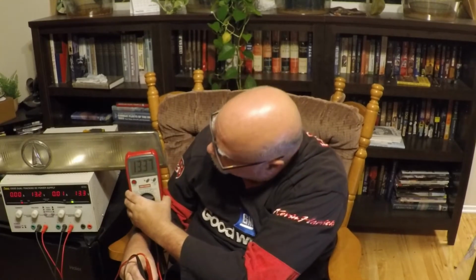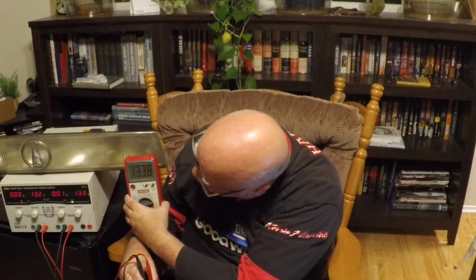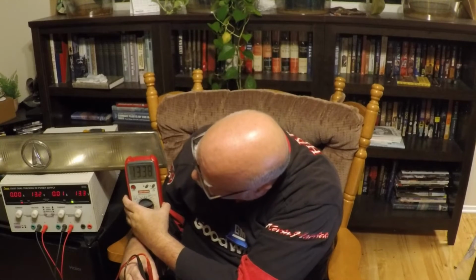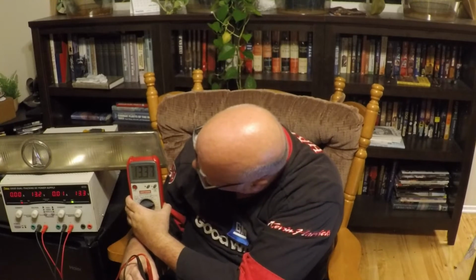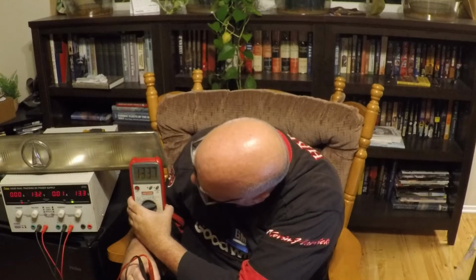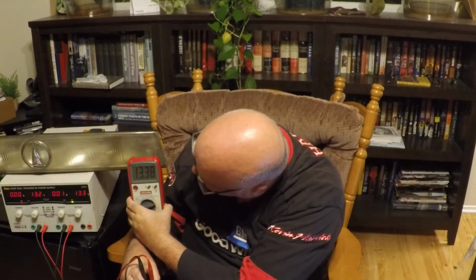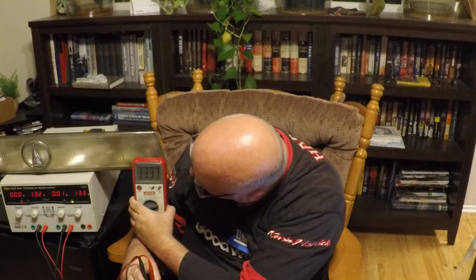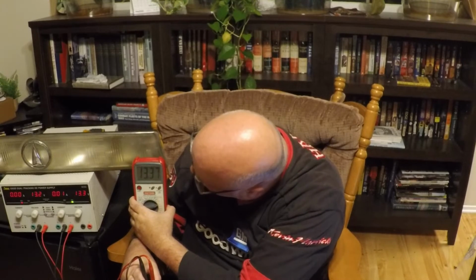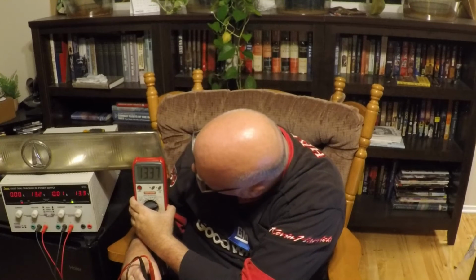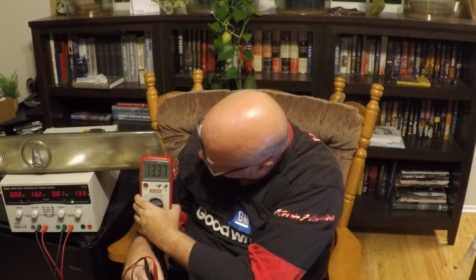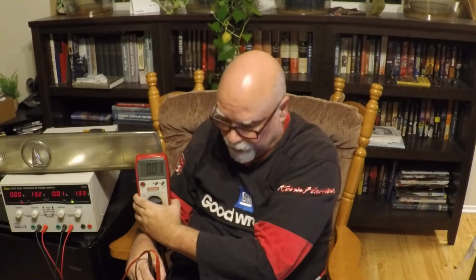Let me hold that up. So you see on there it's displaying 13.3 at no amperes on the power supply unit itself, and it only reads out to 3 digits. This one reads out 4, so it's showing 13.37. That's telling me the tracking between these two is pretty accurate, and I would have confidence in either of these reading correctly.